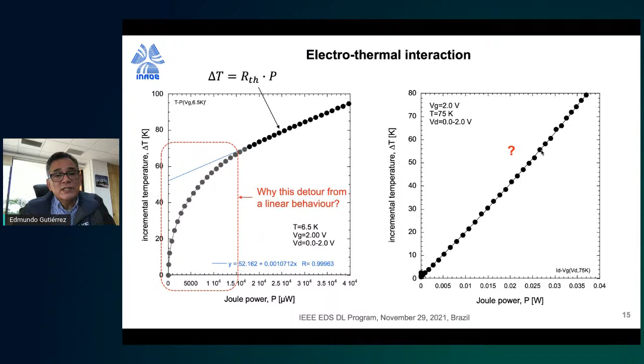Okay, this is what I was telling you. If we are operating the device pretty close to 70, let's say 80 Kelvin, 75 Kelvin, the thermal resistance is, I would say, pretty constant. Then we should expect a straight line. A correlation between the temperature and the joule power should be a straight line. But if we move to lower temperatures below 50 Kelvin, then the thermal resistance is changing quite a lot, from very large values to these very low values. And that is the reason why we are having this nonlinear behavior at very low temperatures.